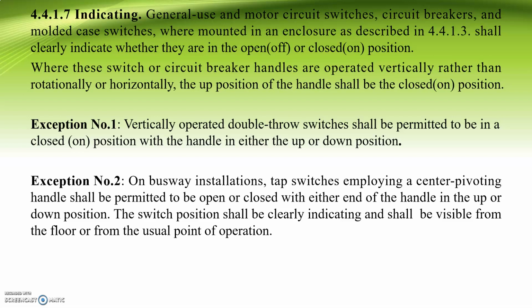Exception number 2: on busway installations, tap switches employing center pivoting handles shall be permitted to be open or closed with either end of the handle in the up or down position. The switch position shall be clearly indicated and shall be visible from the floor or from the usual point of operation.